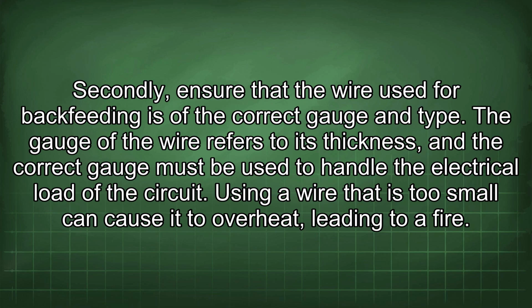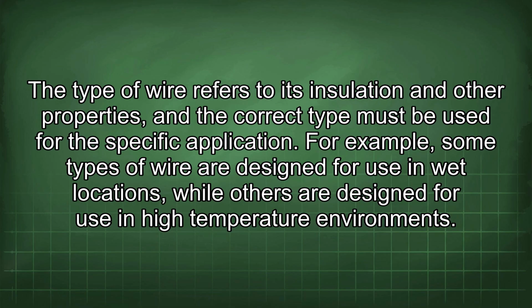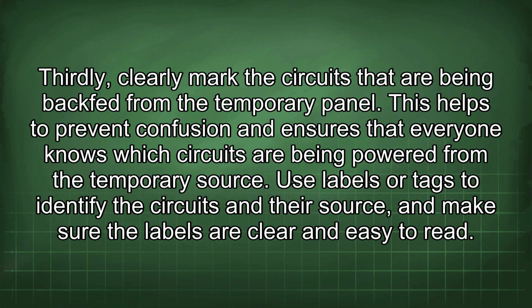Secondly, ensure that the wire used for backfeeding is of the correct gauge and type. The gauge of the wire refers to its thickness, and the correct gauge must be used to handle the electrical load of the circuit. Using a wire that is too small can cause it to overheat, leading to a fire. The type of wire refers to its insulation and other properties, and the correct type must be used for the specific application. For example, some types of wire are designed for use in wet locations, while others are designed for use in high-temperature environments.